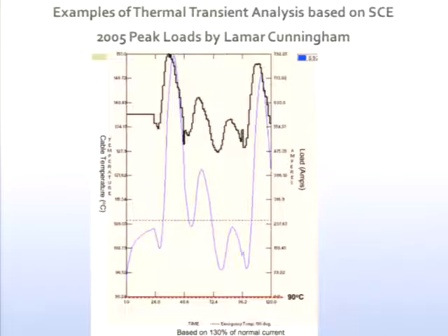And another piece of evidence is something that Lamar Cunningham reported at our first Berkeley workshop, which was 2 years ago. I think these are actual measurements of temperature in the cable. These numbers here, this is 96 degrees, 102, 103. And you can see the temperatures become quite high. This is the current passed through this particular cable. So indeed, these cables get hot.